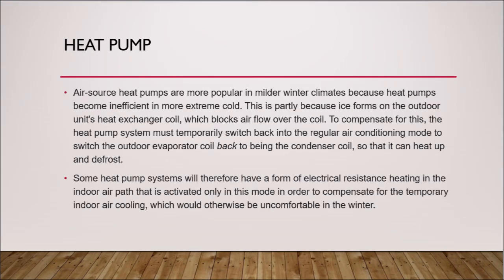Air source heat pumps are more popular in milder winter climates because heat pumps become inefficient in more extreme cold. This is partly because ice forms on the outdoor unit heat exchanger coil, which blocks airflow over the coil. To compensate for this, the heat pump system must temporarily switch back into regular air conditioning mode to switch the outdoor evaporator coil back to being the condenser coil so that it can heat up and defrost. Some heat pump systems will therefore have a form of electric resistance heating in the indoor air path that is activated only in this mode, in order to compensate for this temporary indoor air cooling, which would otherwise be uncomfortable in the winter.